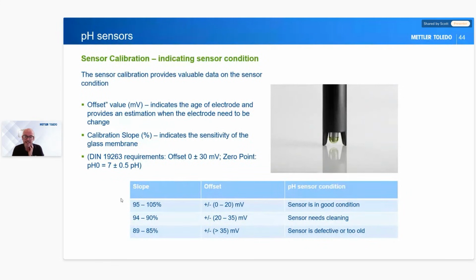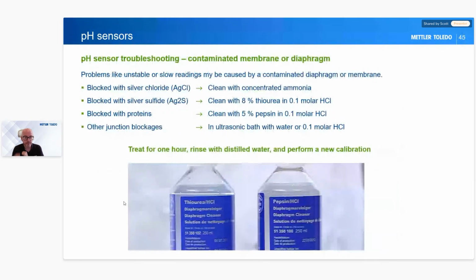And if that is the case, then these slopes are correct. And if you're getting something that's way out of slope or offset, then either your sensor's defective or old, and you need to make some fixes to the electrode, which we'll go through now, or you need a new electrode to replace. So if something is wrong with our electrode, we have some cleaning solutions here.